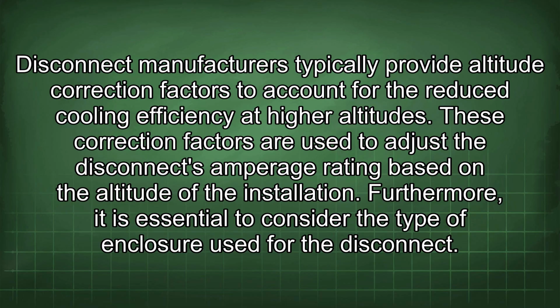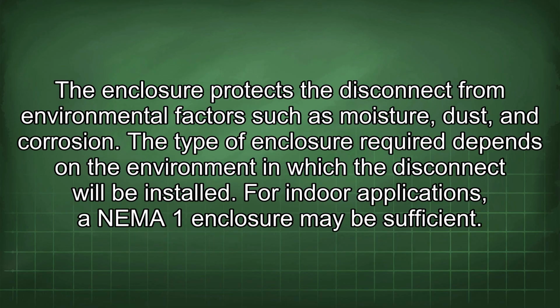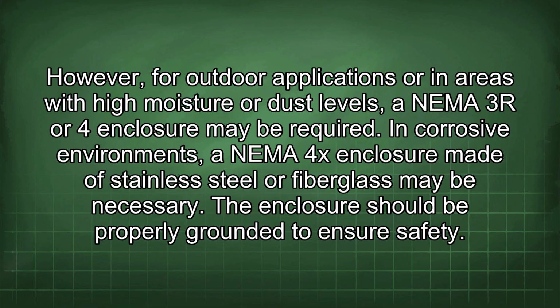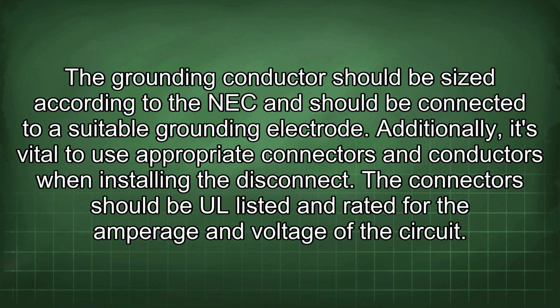Furthermore, it is essential to consider the type of enclosure used for the disconnect. The enclosure protects the disconnect from environmental factors such as moisture, dust, and corrosion. The type of enclosure required depends on the environment in which the disconnect will be installed. For indoor applications, an NEMA 1 enclosure may be sufficient. However, for outdoor applications or in areas with high moisture or dust levels, a NEMA 3R or 4 enclosure may be required. In corrosive environments, a NEMA 4x enclosure made of stainless steel or fiberglass may be necessary. The enclosure should be properly grounded to ensure safety. The grounding conductor should be sized according to the NEC and should be connected to a suitable grounding electrode.